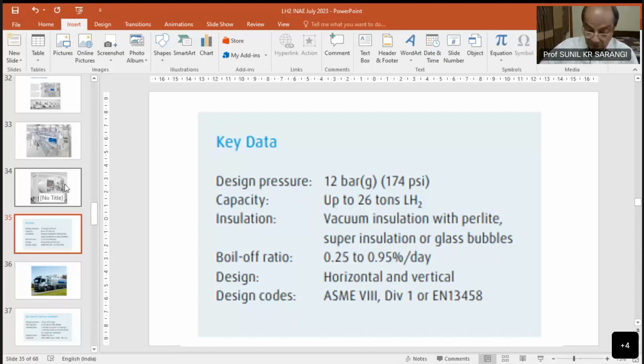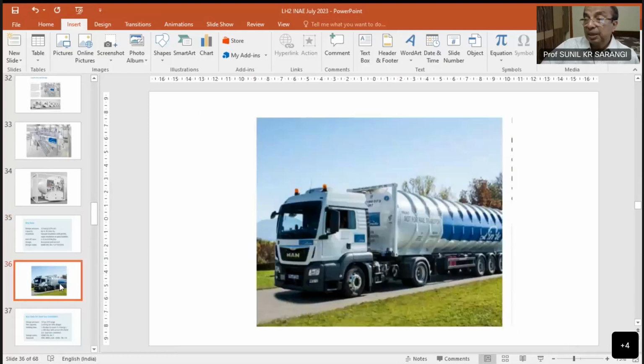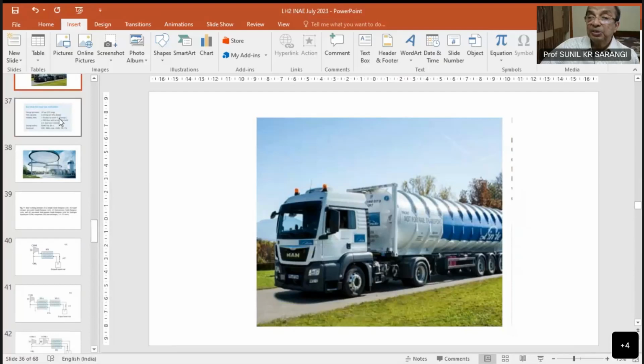Super insulation involves annular spaces at high vacuum, around 10 to the power minus 6 millibar, with aluminized mylar reflectors. This is how extremely good insulation is obtained with acceptable boil off ratio - fill up a tank and it will last 400 days. Vertical, horizontal, and ASME Section VIII designs are fairly standard.